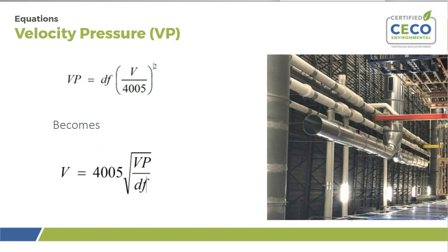Once we have measured the velocity pressure, we can rearrange our equation and determine the velocity that causes the velocity pressure. This is because there is a direct relationship between the velocity pressure and the velocity within a duct. For a quick approximation regarding actual conditions, one can assume that the actual density and the standard density are the same. And if we make this assumption, then the density factor, the dF, becomes 1.